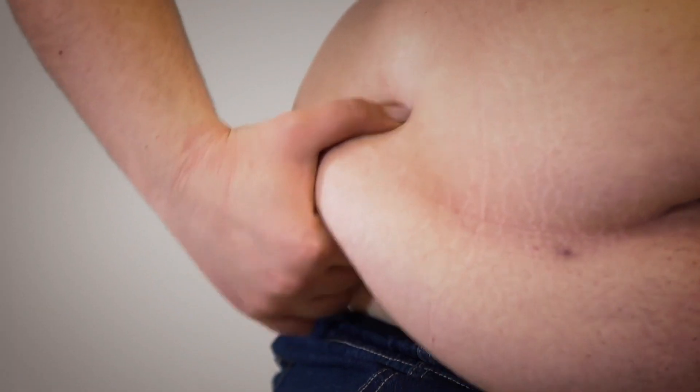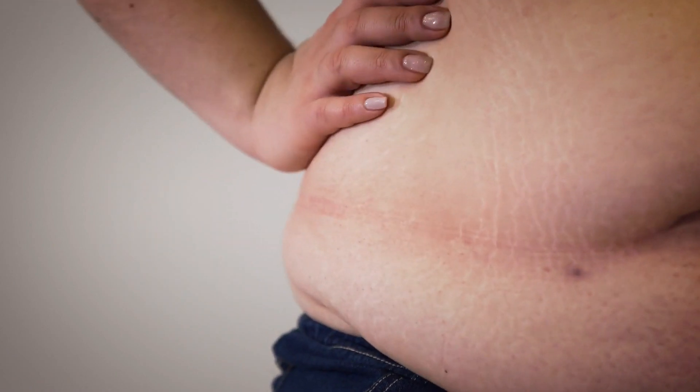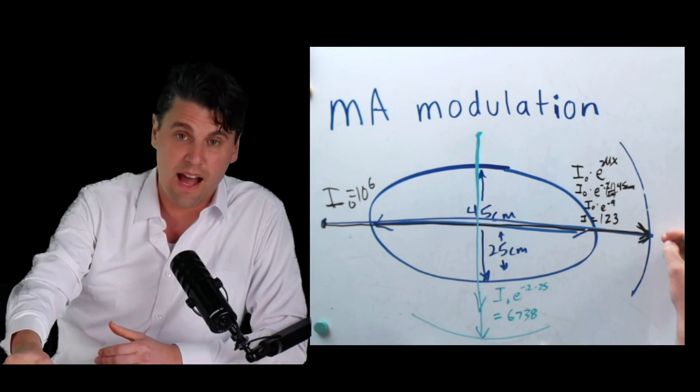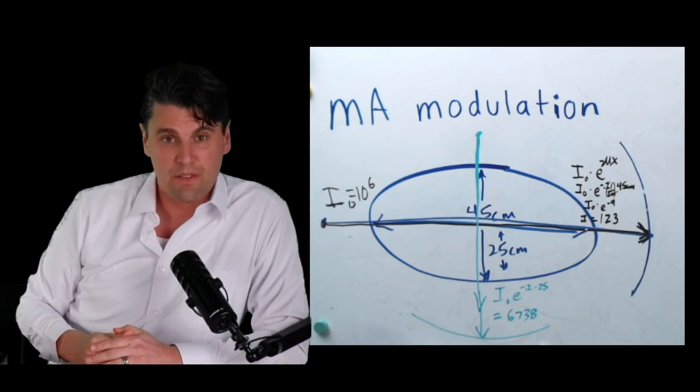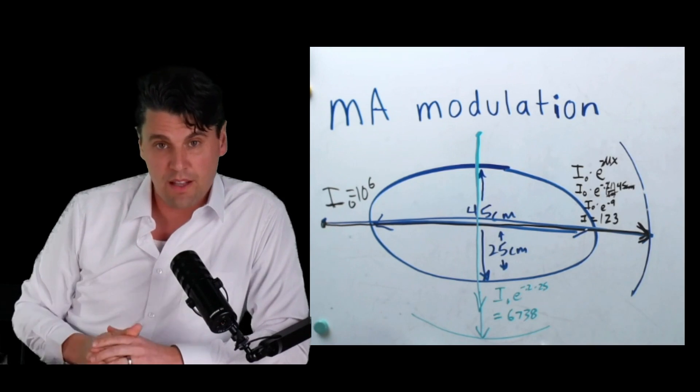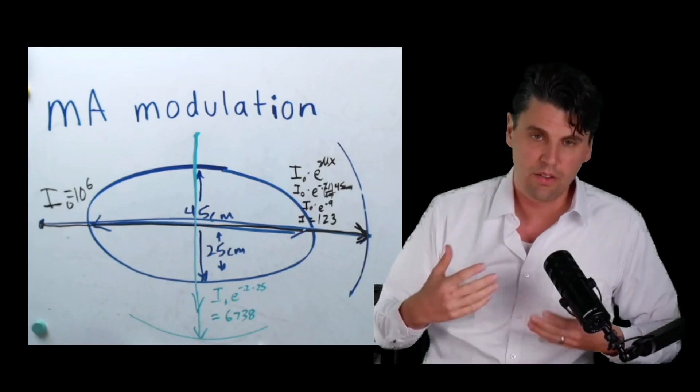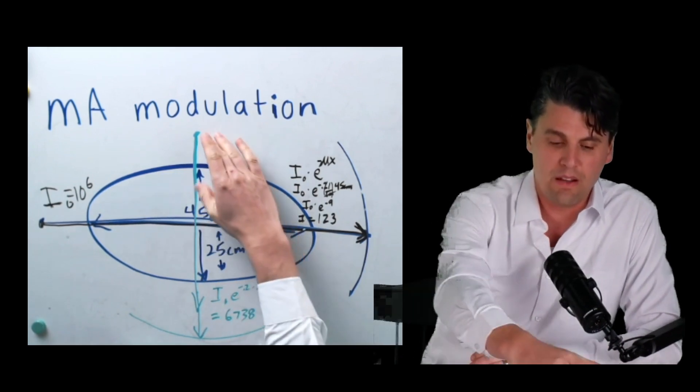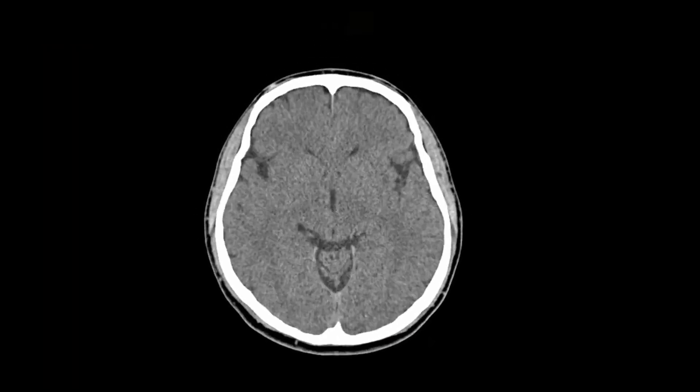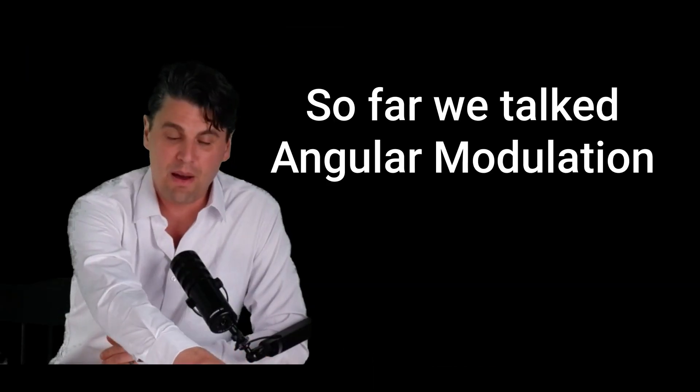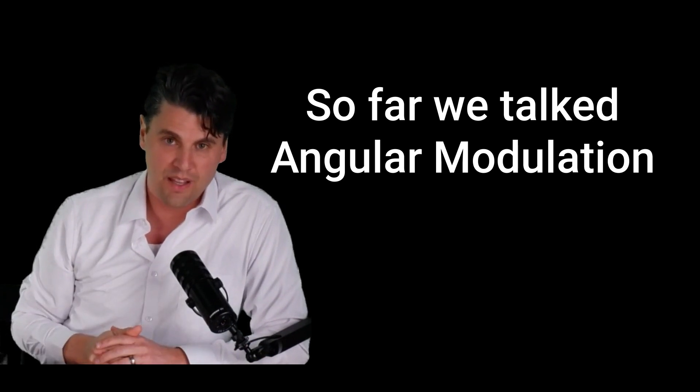And in the case of bones in the hips or in a large abdomen, this can be even worse. And especially you can see significant artifacts when you start really reducing the dose. If you're going to a monitoring type scan where you're going to have really low dose in your images. One other option, we could change the amount of time that we take per view, but then you're going to end up with angular blurring. Another thing that you could do to change the modulation would be to actually change the KVP. But like we talked about before, KVP determines the contrast in our imaging. So it's not as easy to change the KVP because then you'd be dealing with different contrasts for these rays and different contrasts for these rays. So it's not a simple project then to actually put those together to make one consistent CT image. And that's why mA modulation is really the standard for changing the dose in our x-ray images.